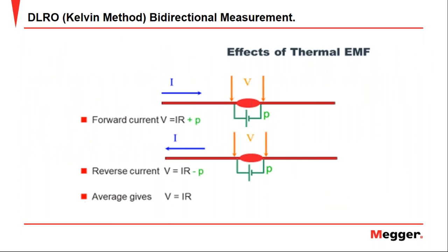What do we mean when we talk about bidirectional? We do this measurement when we want to eliminate the Seebeck or thermoelectric effect. The Seebeck effect is a phenomenon in which a temperature difference between two dissimilar electrical conductors or semiconductors produces a voltage difference between the two substances. If we measure in only one direction, a voltage will be generated and can alter the measurement. But if we do it in both directions, we can eliminate the effect and the reading will be as accurate as possible.